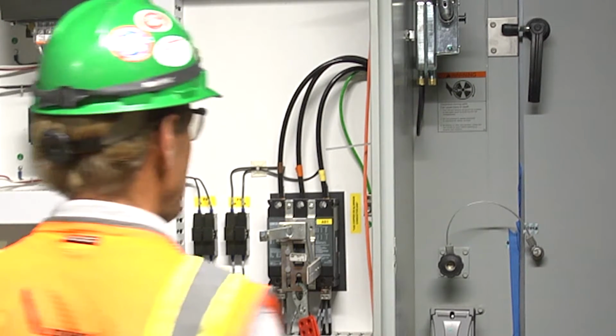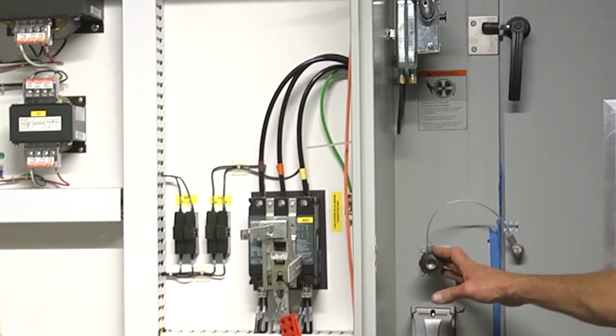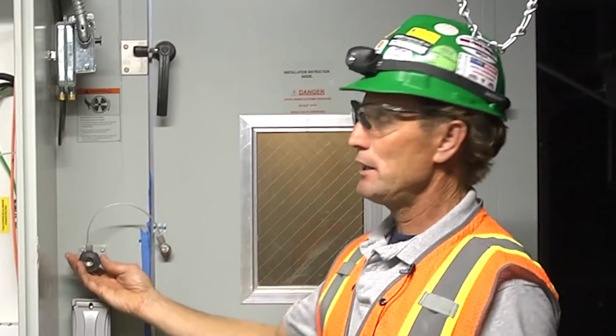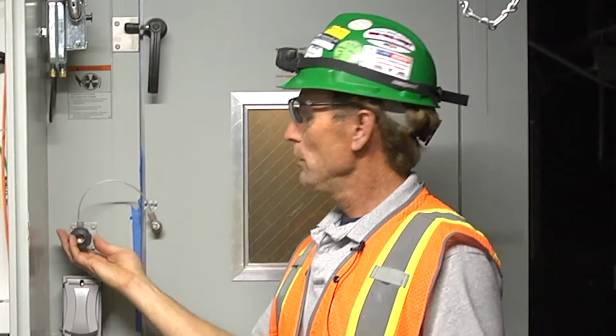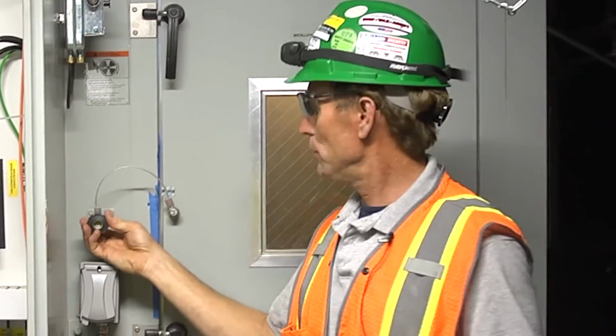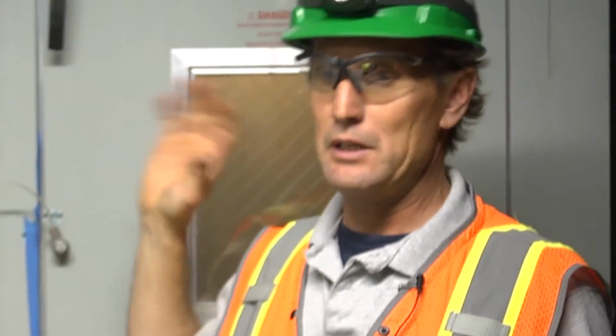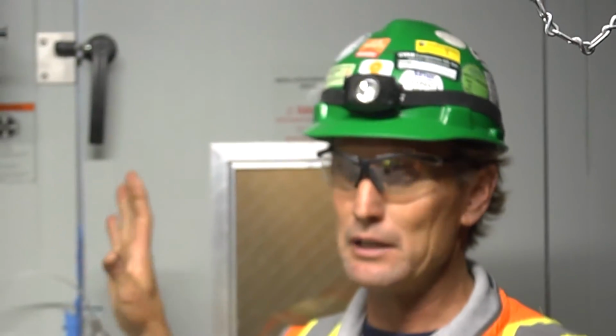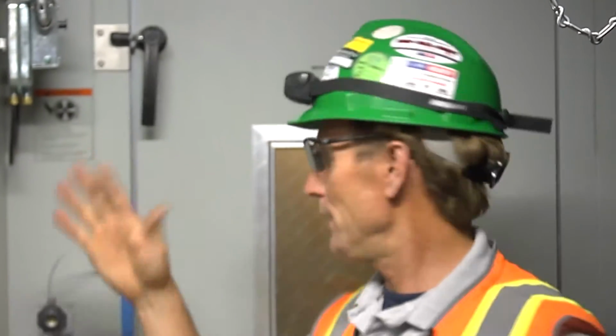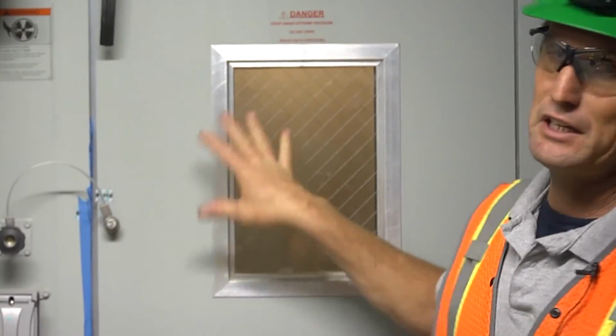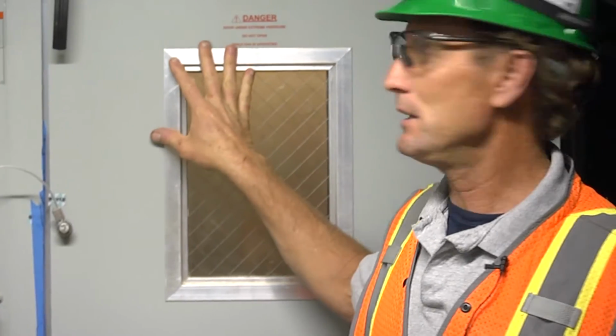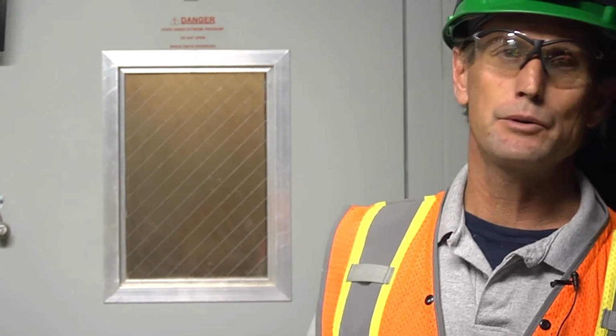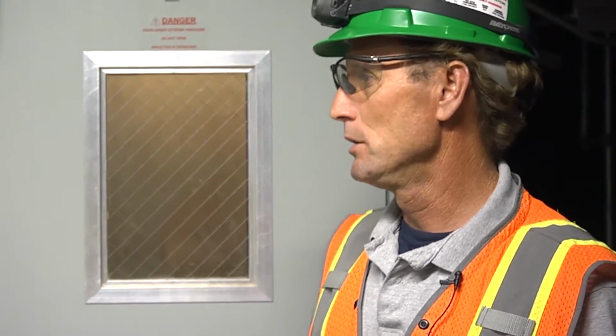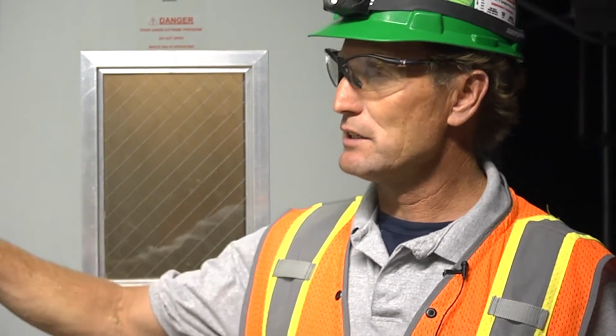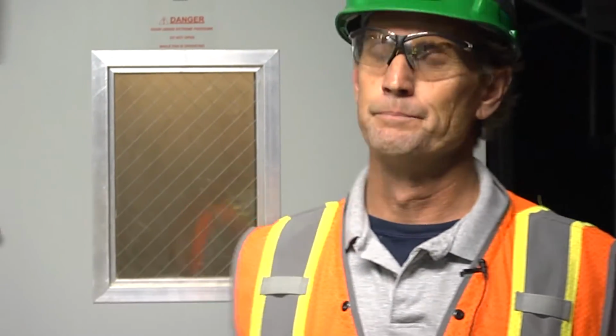So as far as other safeties for entering the unit, we have an access door here to the supply fan motors, and a door switch here. When this screw is screwed out, it interrupts the drives and ensures that the drives are secured and off, and you can then enter into the supply fan motor cabinet and service the motors and inspect the motors. But to de-energize the unit, that's done here.